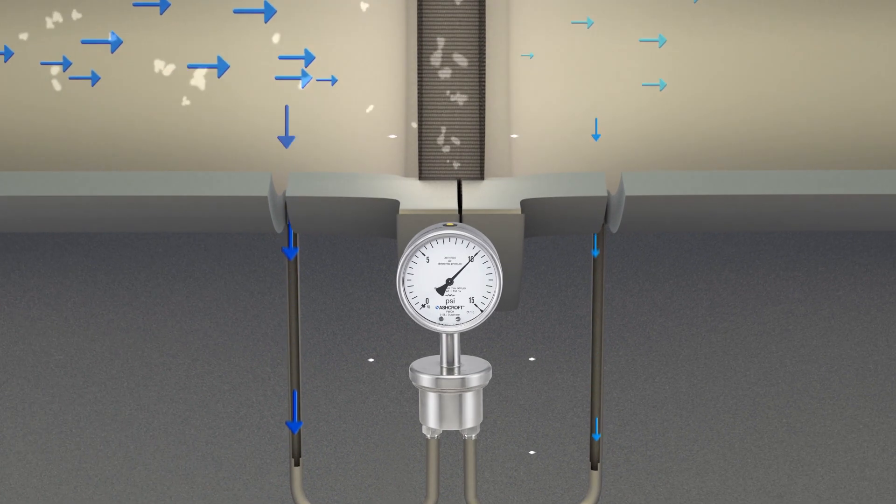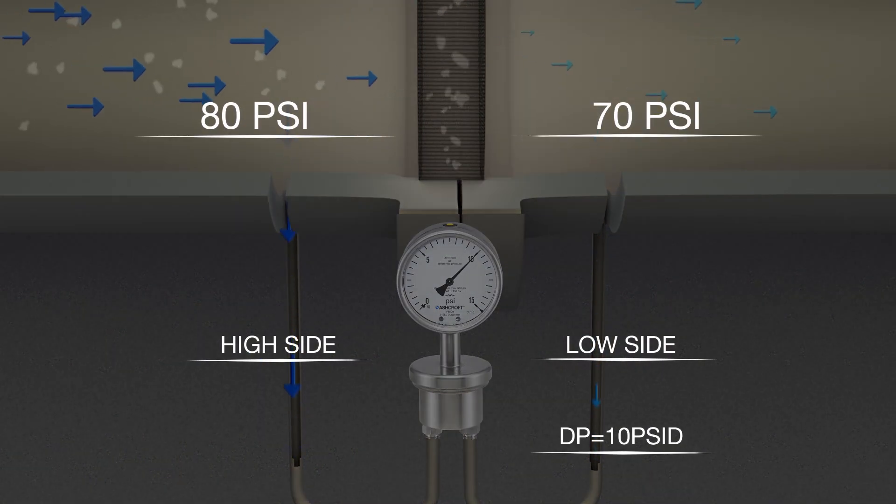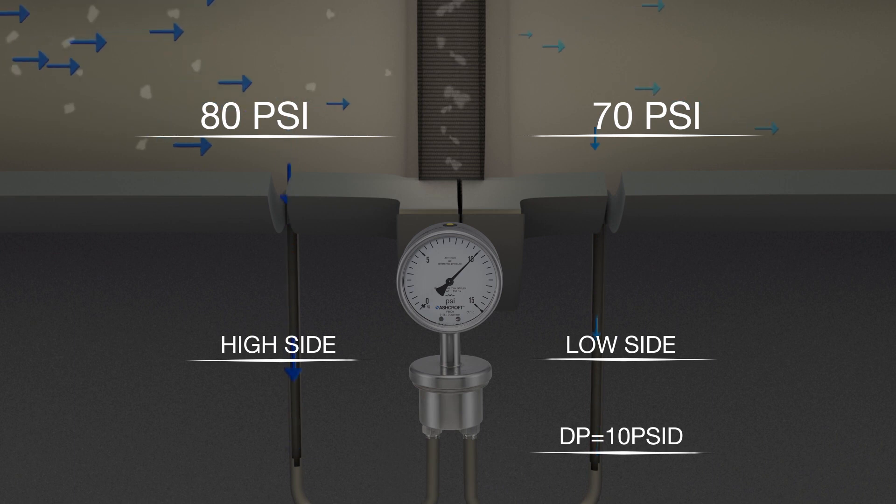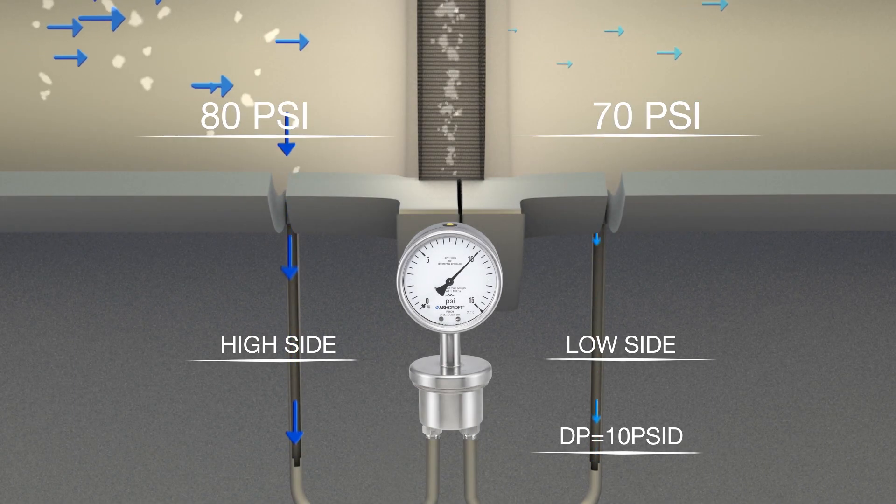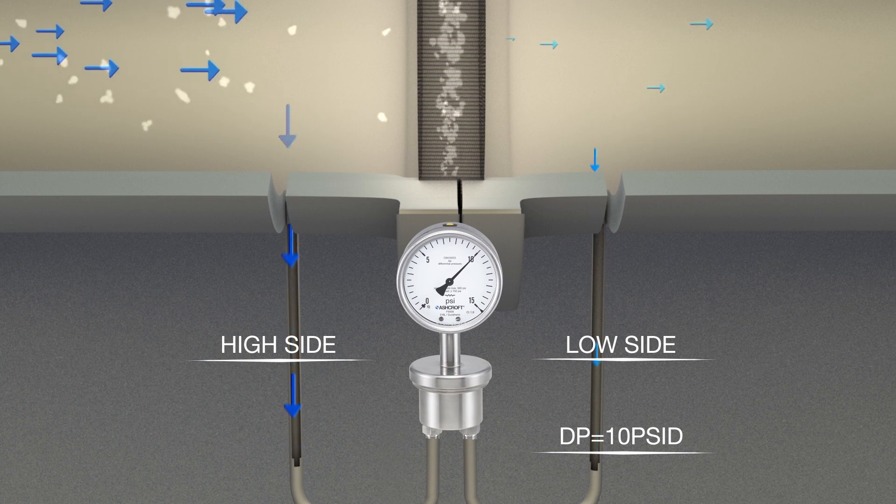The saturation point will be indicated when the delta P value reaches a predetermined threshold. This value is derived from a calculation that factors in the flow rate, fluid viscosity and filter characteristics.